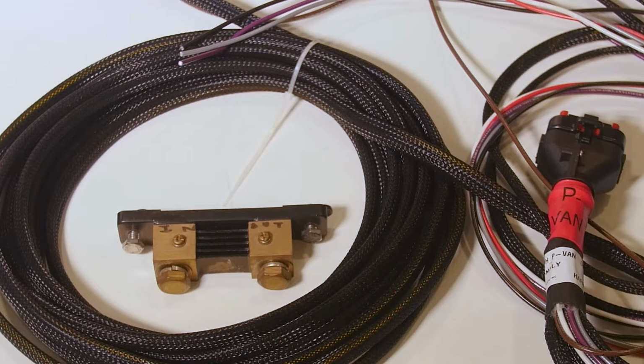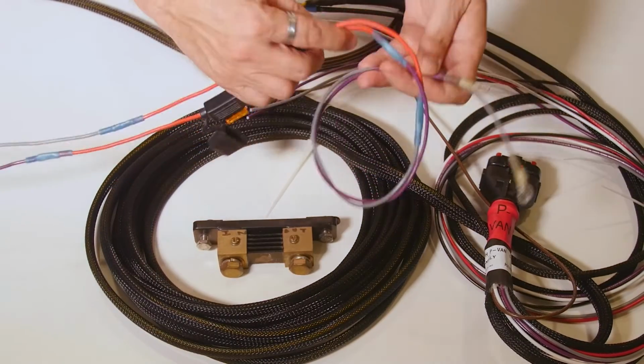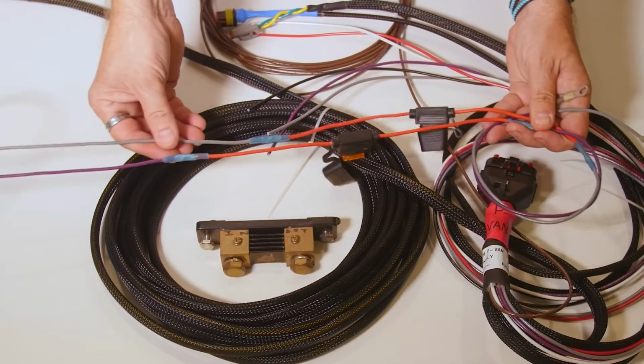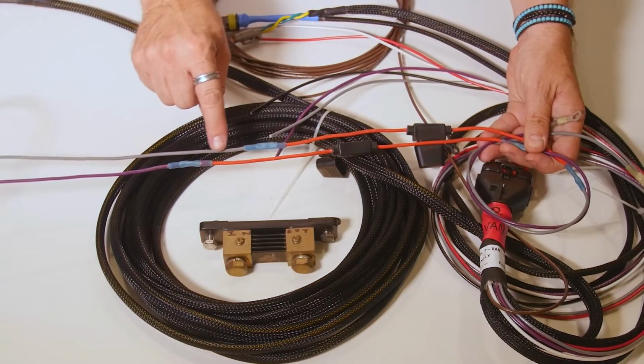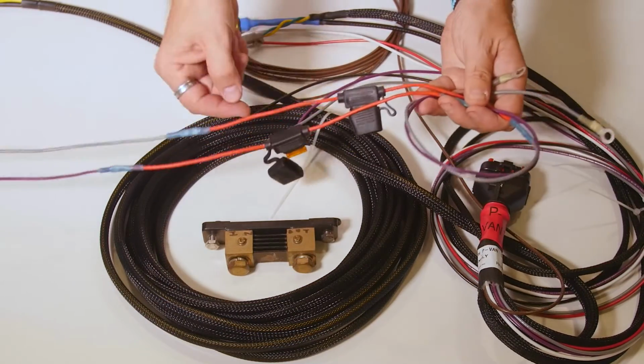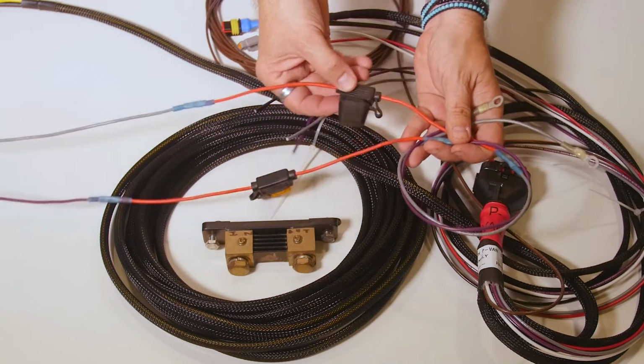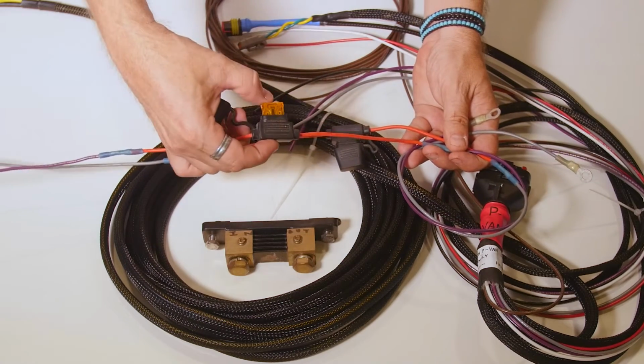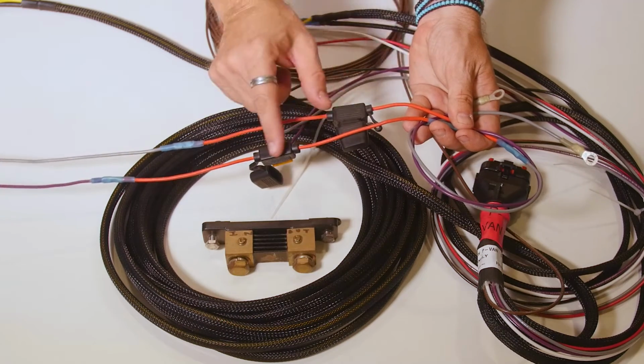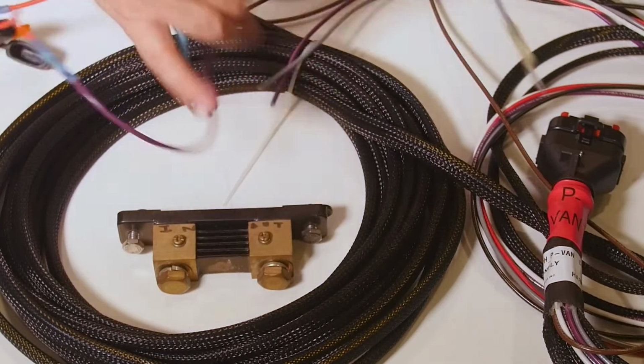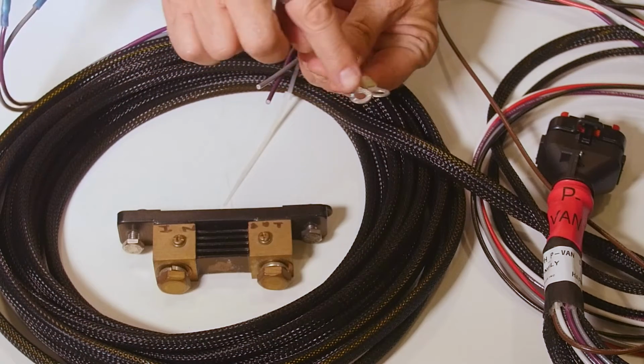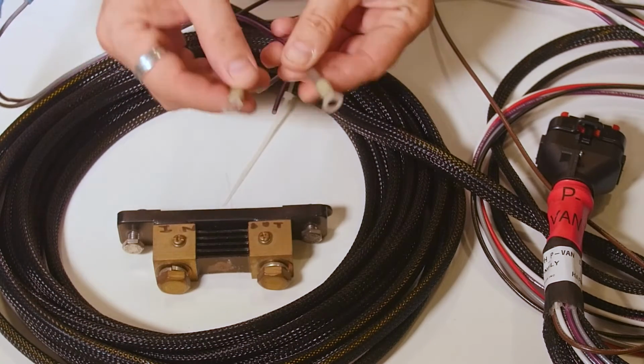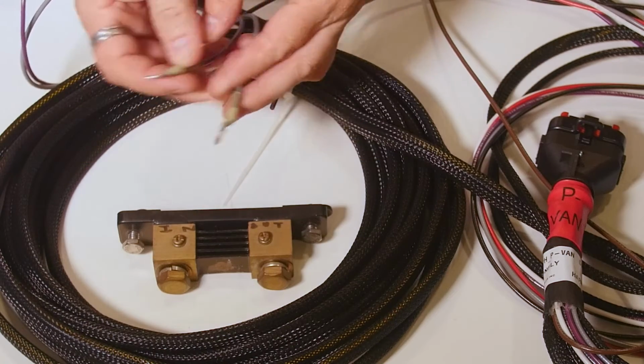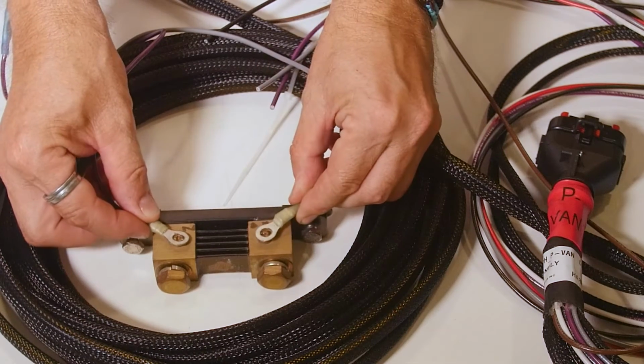Now, these should also be fused. So here's an example of another harness where we've gone ahead and spliced onto the gray and purple wires with inline fusing. We have a 5 amp fuse on both wires, and then on the end of those wires we've crimped on ring terminals, and those ring terminals connect up to the shunt on these terminal locations.